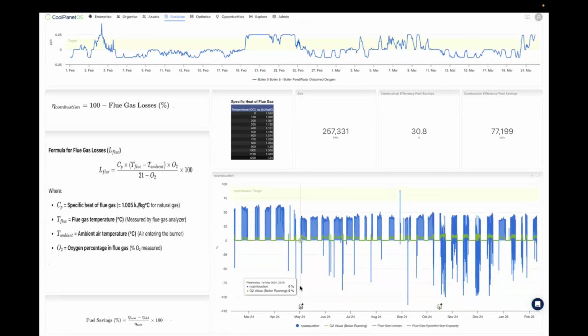So what happened here was the boiler was down for maintenance and insurance checks, and the same controls weren't implemented as before that check took place. And then this drop in efficiency was when the heat pump was installed. So because the heat pump was taking up 30 to 40% of the thermal load on site here, this boiler's burner needed to get recalibrated to deal with its new nominal load. And it was as simple as that. But if we didn't have the data and really interrogate it, and because the savings were so healthy, this could have been something that we missed.